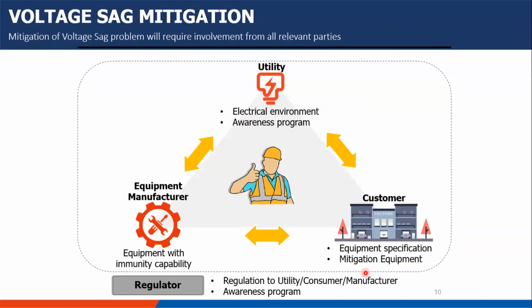Customers also have a role to play in mitigating voltage sag, which is to purchase equipment with a specification that can ride through a voltage sag event if they have sensitive machinery, and also to install mitigation equipment if they have sensitive equipment that is unable to work during a voltage sag. The equipment manufacturer also has a role, to develop equipment with immunity capability that can ride through voltage sag. So this triangle shows that voltage sag mitigation is not a solo program. It needs all parties. The regulator also has a role, which is to regulate the utility, customer and manufacturer, and also produce some awareness programs. So all relevant parties have their own role in mitigating voltage sag.